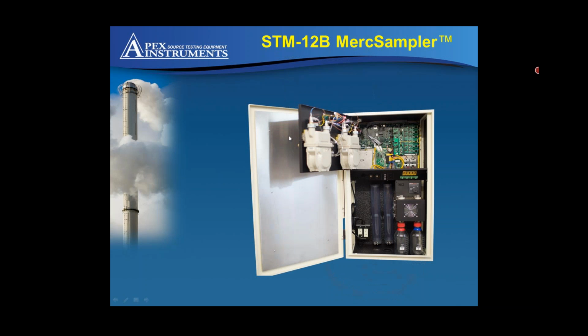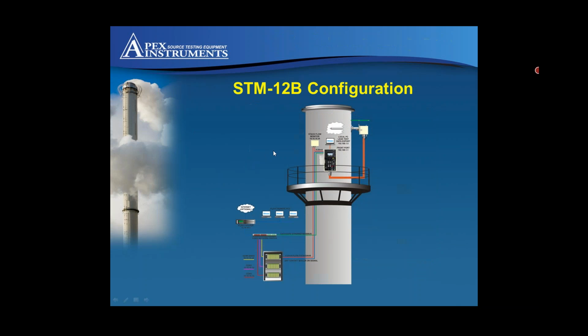What signals do we take out of the box that have to go back down to the DAS? It's Ethernet. Is that fiber Ethernet? We come out with just RJ45, just Ethernet. If you put a fiber converter there, we plug right into that. Okay. So if you're running an Ethernet down to the DAS, you'd use that same Ethernet to get your flow signal back.